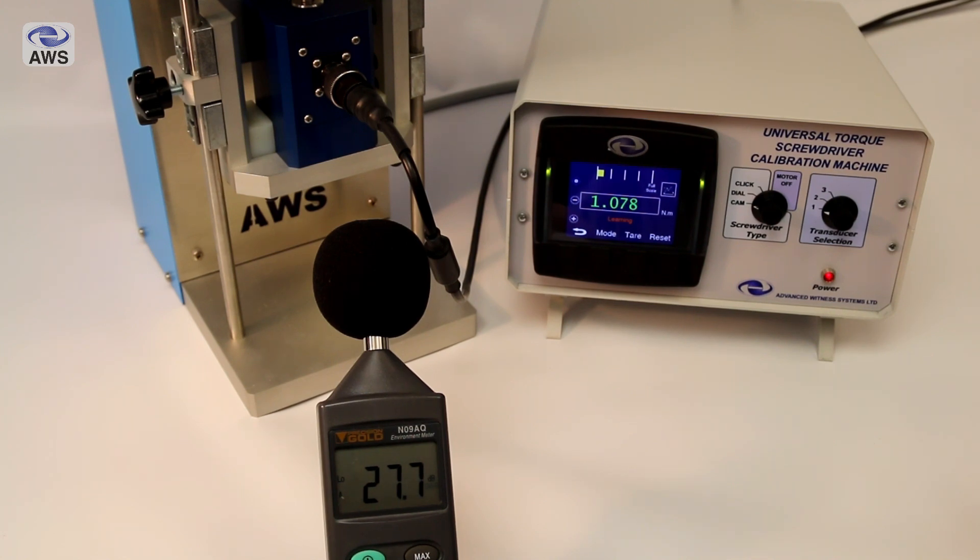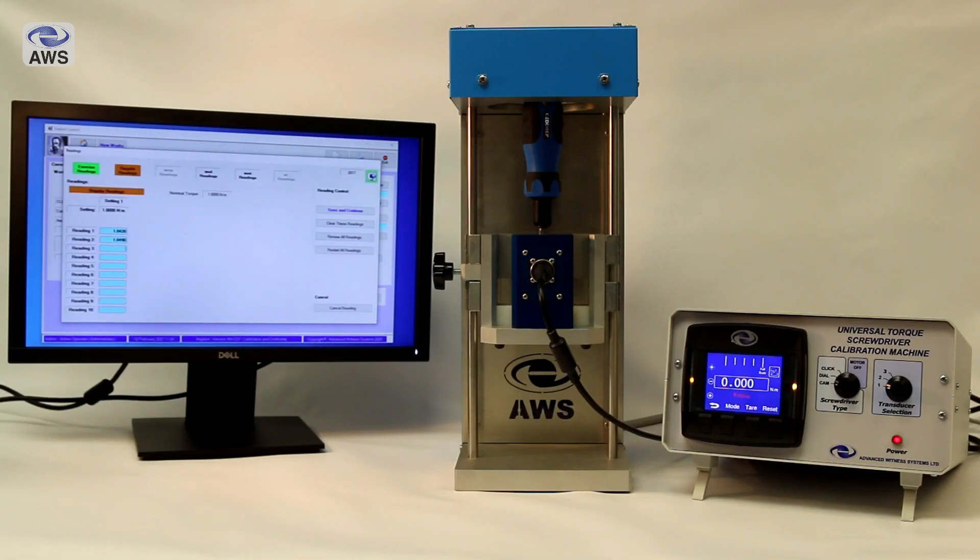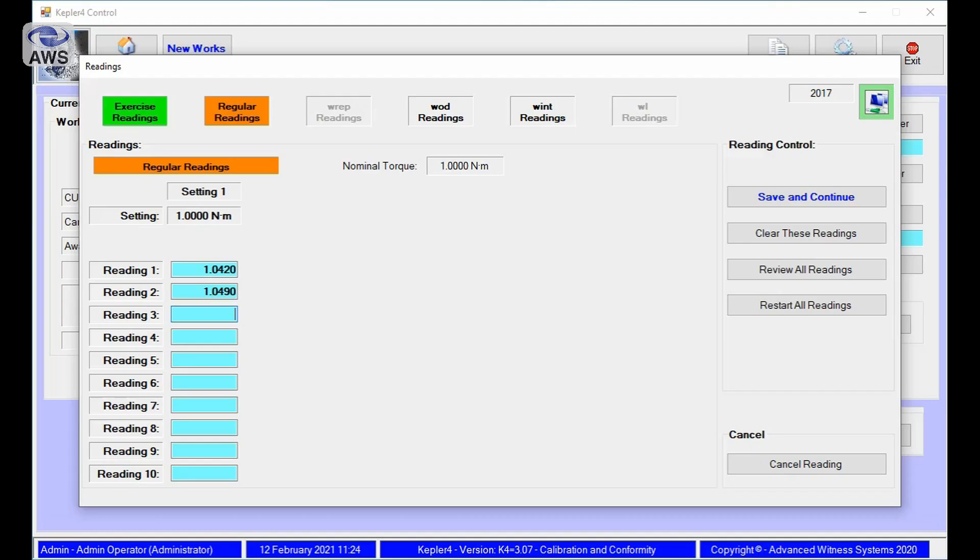As with our universal torque wrench calibration machine, this can be used in collaboration with the AWS Kepler4 software, which takes values straight from the display, speeding up completion of the calibration or certification process to ISO 6789-2017.